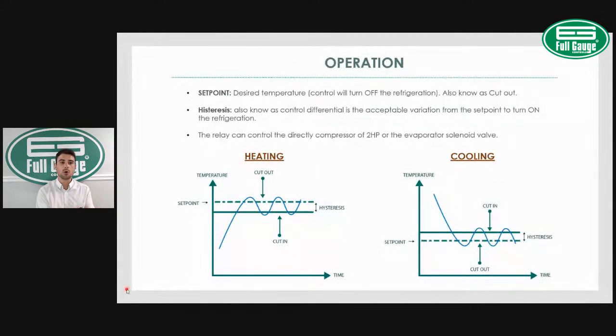Under the heating mode, your set point is the upper temperature, the cutout. Again, the cutout temperature is going to be the warmer temperature. So for example, if you set to heating, the controller will cut in at the differential and the temperature will rise to the set point temperature, which is the cutout. So on the heating mode, the set point is on the temperature rise, and on the cooling mode, the set point is on the temperature fall.